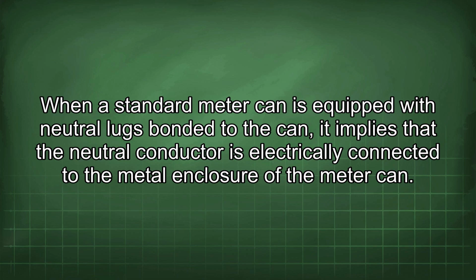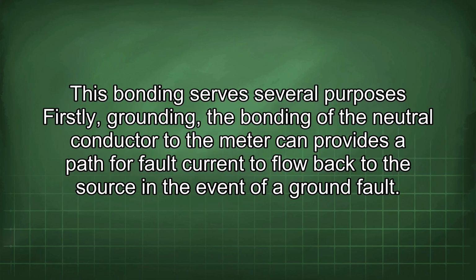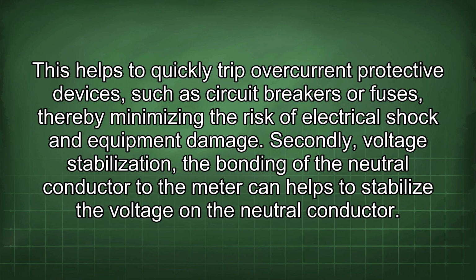When a standard meter can is equipped with neutral lugs bonded to the can, it implies that the neutral conductor is electrically connected to the metal enclosure of the meter can. This bonding serves several purposes. Firstly, grounding. The bonding of the neutral conductor to the meter can provide a path for fault current to flow back to the source in the event of a ground fault. This helps to quickly trip overcurrent protective devices such as circuit breakers or fuses, thereby minimizing the risk of electrical shock and equipment damage.